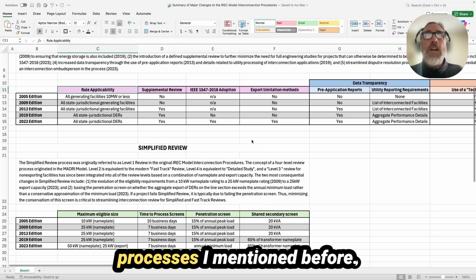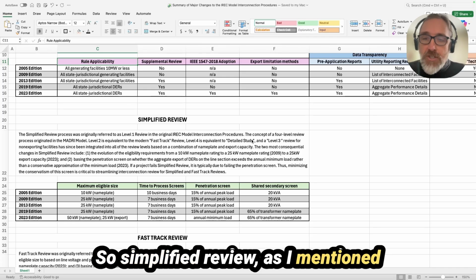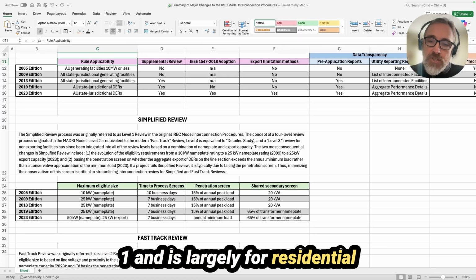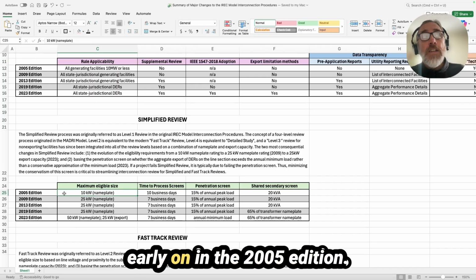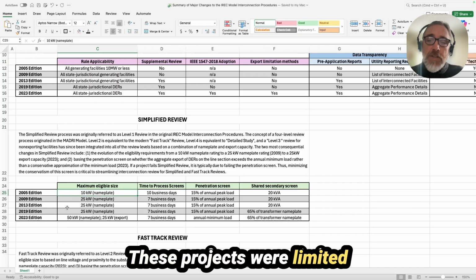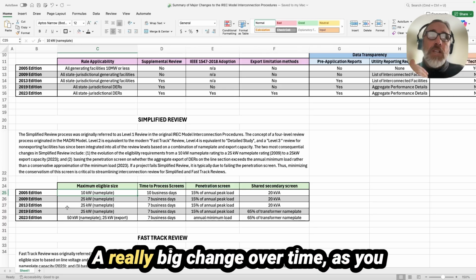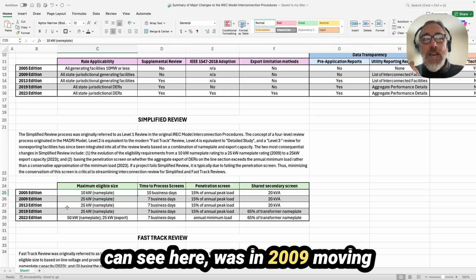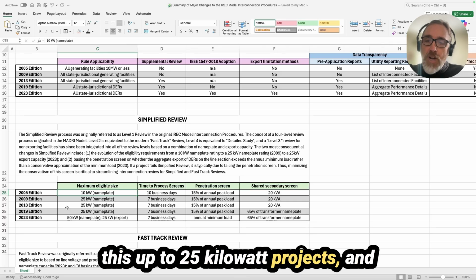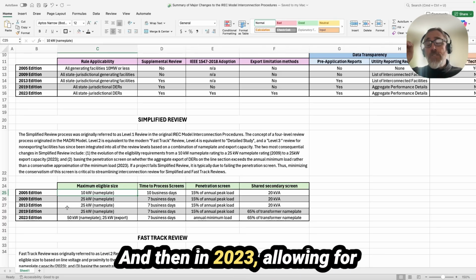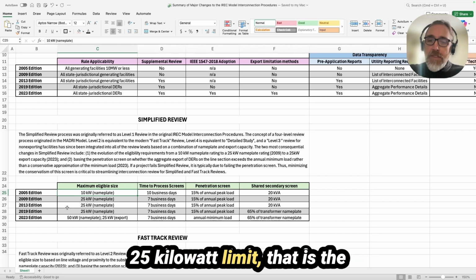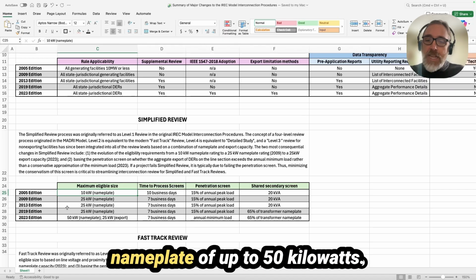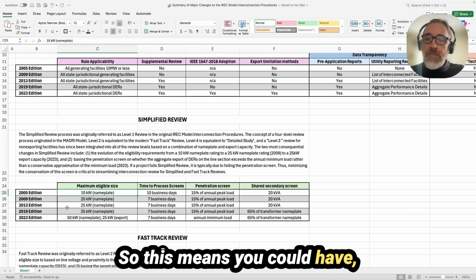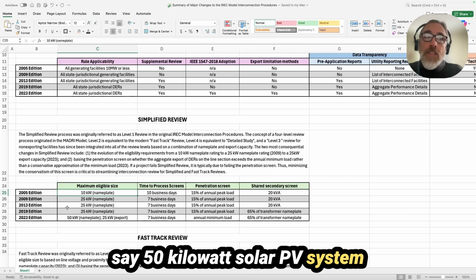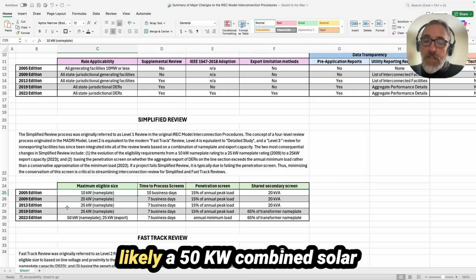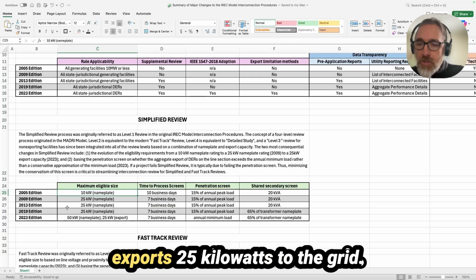All right, let's go down to the review processes I mentioned before. So simplified review, as I mentioned prior, used to be called Level 1 and is largely for residential and small commercial projects. Early on in the 2005 edition, these projects were limited to a nameplate rating of 10 kilowatts or less. A really big change over time, as you can see here, was in 2009, moving this up to 25 kilowatt projects. And this is again on the nameplate rating. And then in 2023, allowing for a 25 kilowatt limit that is the export limit, and allowing a nameplate of up to 50 kilowatts. So this means you could have, say, 50 kilowatt solar PV system that only exports 25 kW, or more likely a 50 kW combined solar and storage project that only exports 25 kilowatts to the grid.